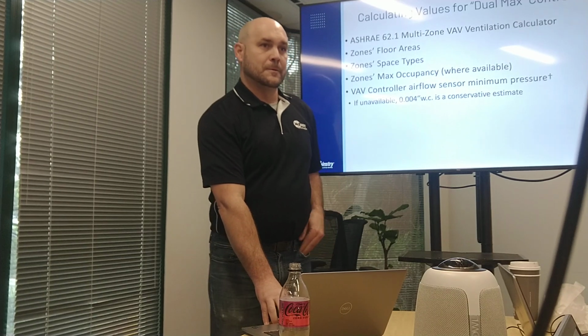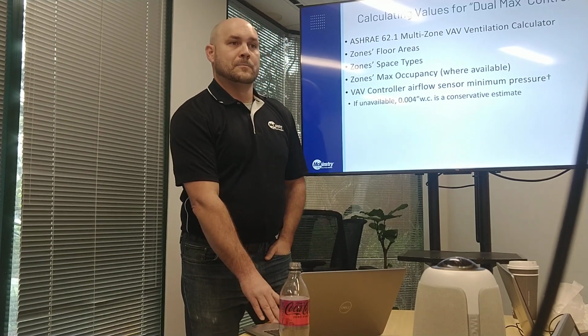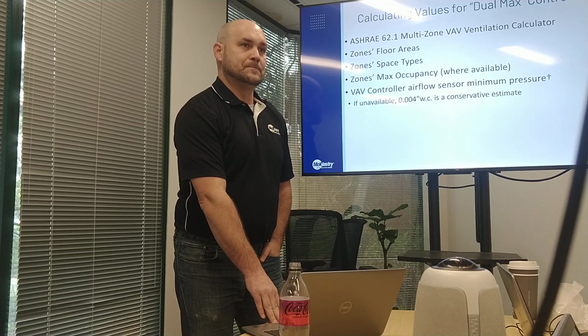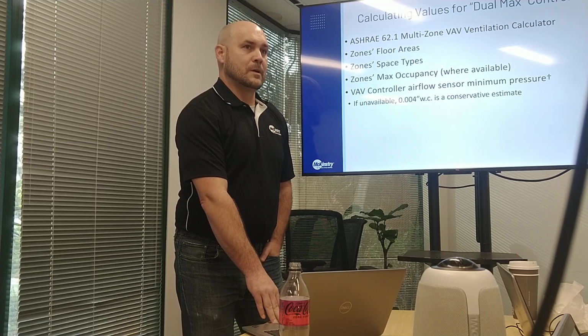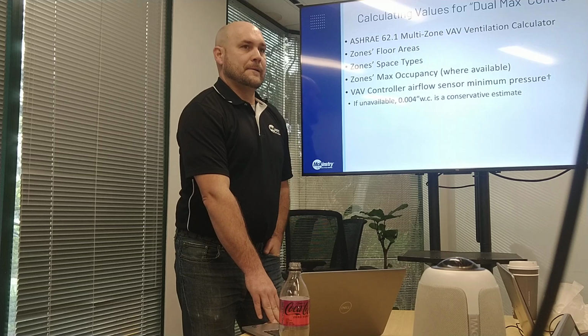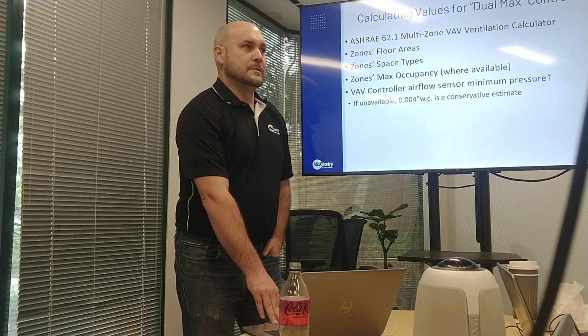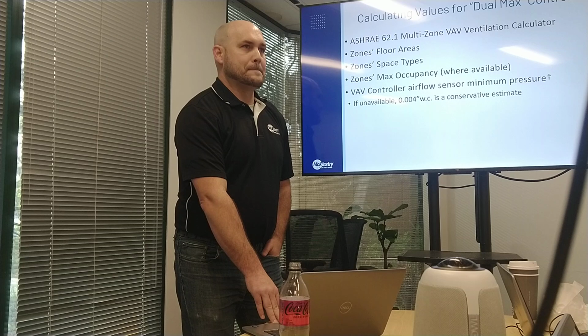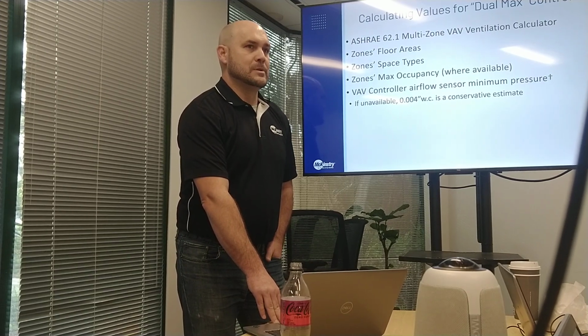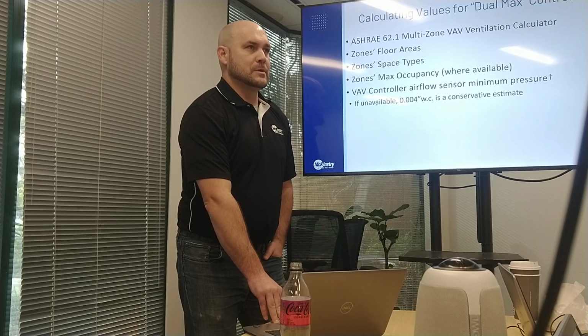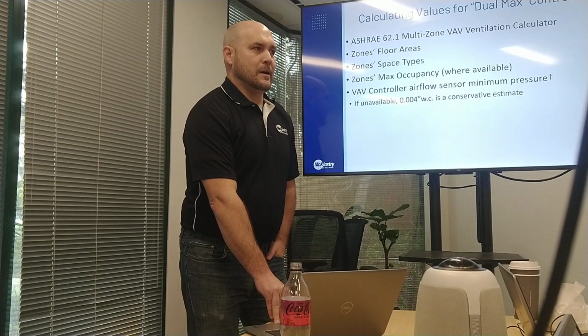Is there a general rule of thumb around percentage airflow in a VAV, what that minimum should be, so that you don't run into the situation where you lose the ability to measure that velocity? Can you simplify it to a base percentage, or does it have to be represented in?